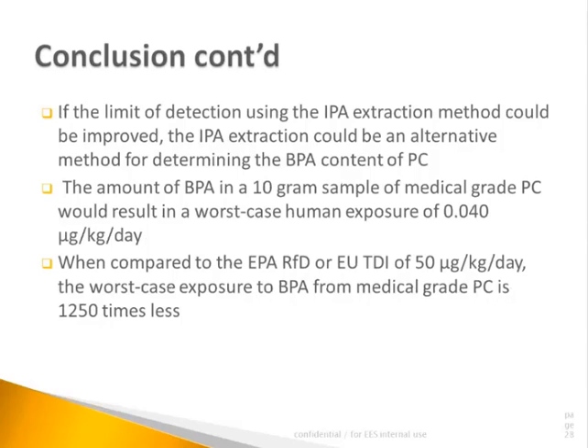Also, IPA extraction could be an alternative method for determining the BPA content of polycarbonate if the detection level could be enhanced. The amount of BPA in a 10-gram sample of the medical-grade polycarbonate will result in a worst-case human exposure of 0.04 microgram per kilogram per day. When this value is compared to the current reference dose from the EPA, which is 50 microgram per kilogram per day, the worst-case exposure from this grade of material is 1,250 times less than the prescribed value from the EPA. Next.